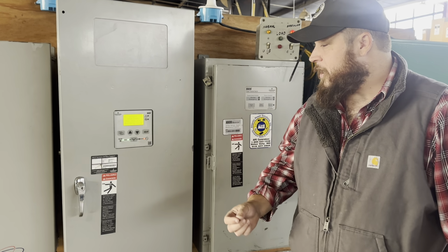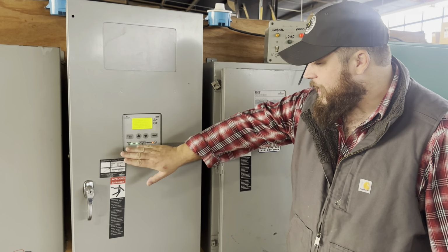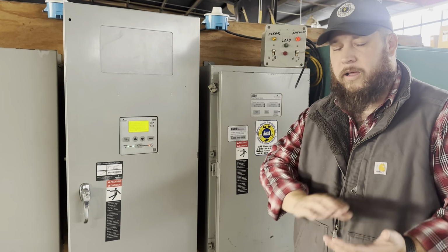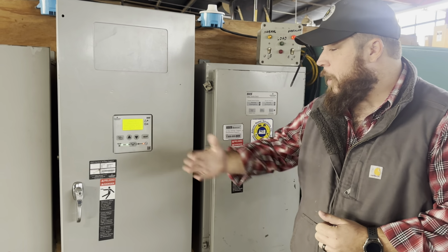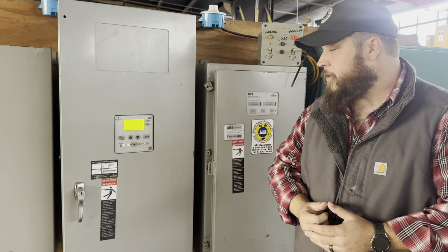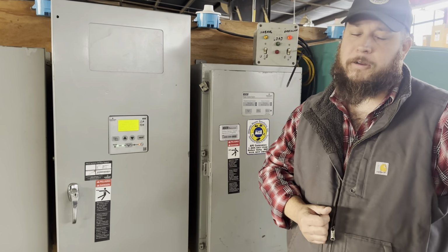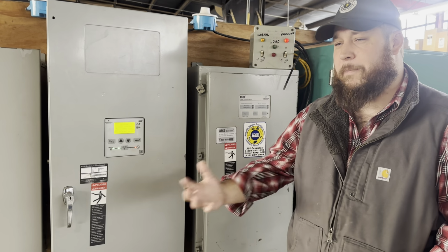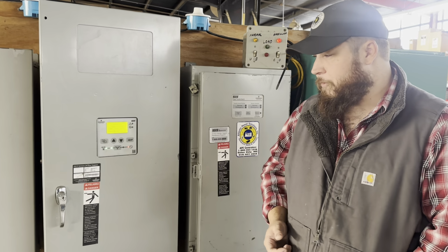So the biggest thing to know is with the generator available, if anything were to happen to utility, the generator's already making power, it can just transfer right back over. But once this goes through its engine cool down, it will cut off the signal to run the generator and the generator will shut off. That being said, it'll remain in auto mode until you have another need further down the road.